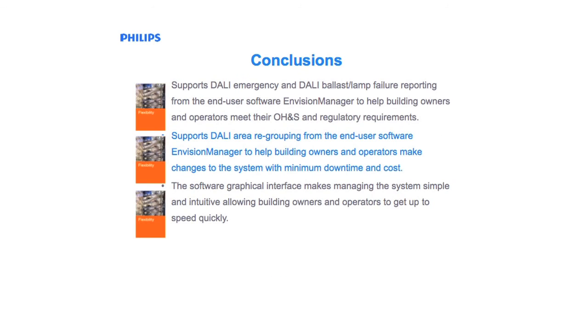Philips Dynalite DALI solution also supports DALI emergency and DALI reporting. This also allows for the system to interrogate each of the ballasts to find out whether its lamp has failed and if the ballast has failed. From this information, a report can be generated through the Envision software to the facility manager of what actions need to be taken.